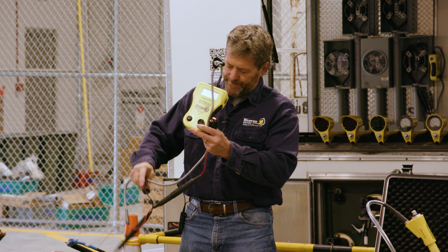Sure enough, it happens. Turn the tool off, we're going to go in phase, hot leg 1 to hot leg 2, in phase. Turn the tool on, look at your voltage. You're seeing 240. When you go to the load, you're hoping to see those counts jump up fast and furious, because you saw 240, you're hoping that the integrity on both legs is good. Sure enough, you turn it on, and it goes to the load, and you're seeing 14 or 16, maybe 12 amp counts or jumps per count. Gets up to about 800 amps, stops counting, holds, those two legs are good.